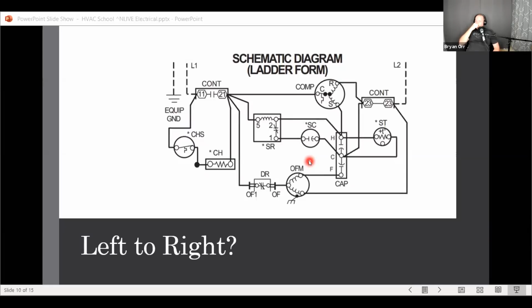And really the only right way in this application is to use either the same sort of contactor or to shunt out one leg of your contactor. You can take one leg of your contactor and just connect from top to bottom with a big piece of wire, and that will essentially shunt that leg out. But again, sometimes that requires double lugging or whatever. So in these cases, this is the one rare case where there isn't another way around that. For example, Trane had a version of this, but it wasn't the same sort of situation where they would just connect to the bottom side, but it wasn't feeding through the compressor winding. I would have to test it.